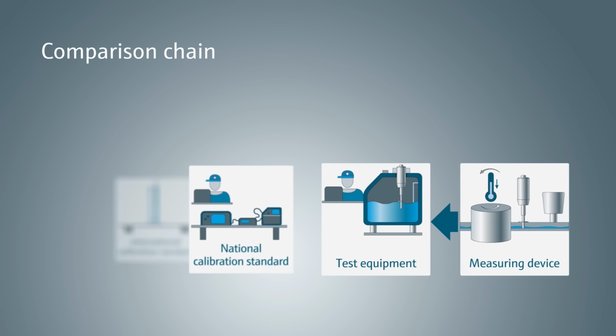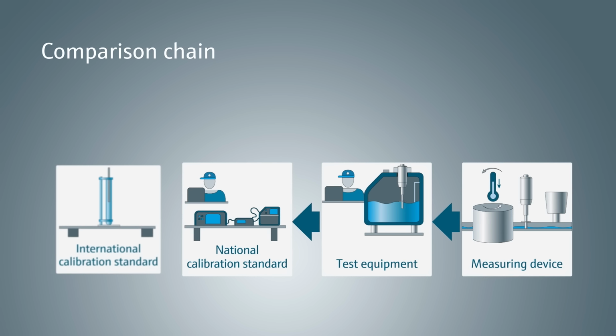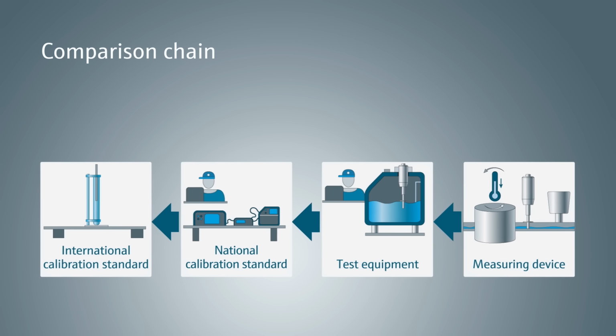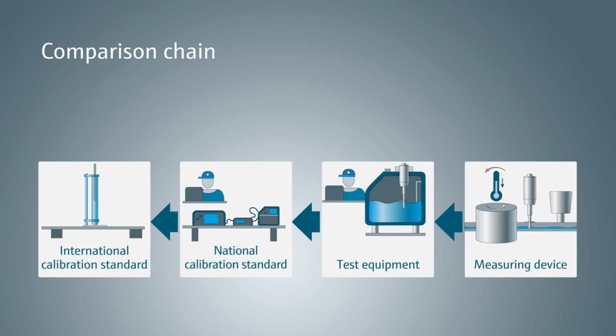One important principle of calibration is complete traceability within the comparison chain. Each device that is to be calibrated is compared to a more precise external reference. This ultimately ensures consistent reference to recognized international calibration standards.